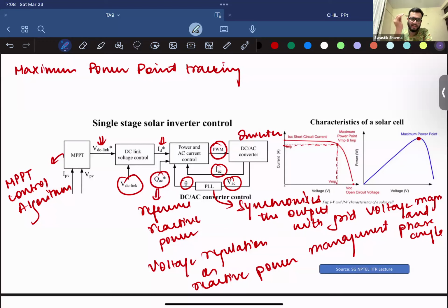Your DC link voltage has to be greater than root two times the RMS voltage, because the real power should flow from DC link to your inverter. If you want to maintain this flow of power, the DC link has to have a higher voltage reference than your peak grid voltage.